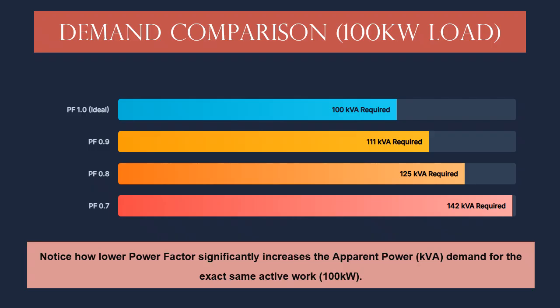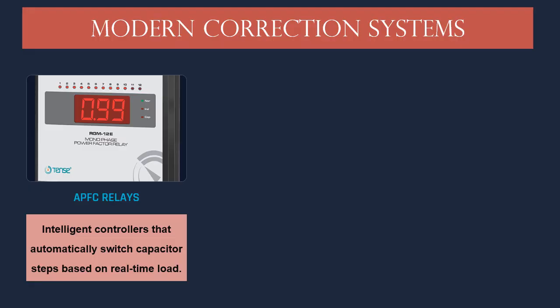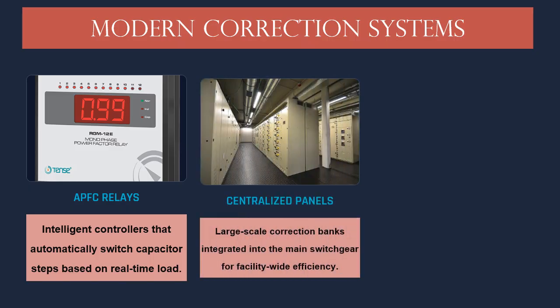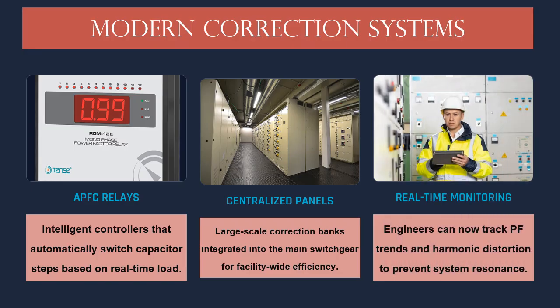Modern correction systems. Correction technology has evolved. We aren't just using static banks anymore. We now utilize intelligent APF relays that monitor the load in real time, automatically switching capacitor steps on and off. We integrate centralized panels into main switchgear, and engineers use advanced monitoring to track harmonic distortion, ensuring the correction process doesn't destabilize the network.